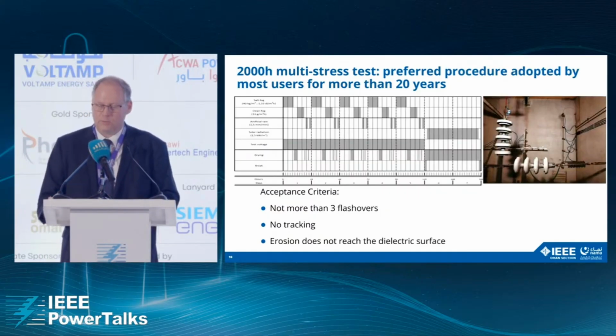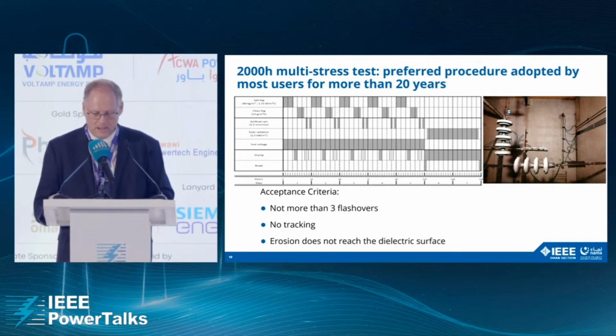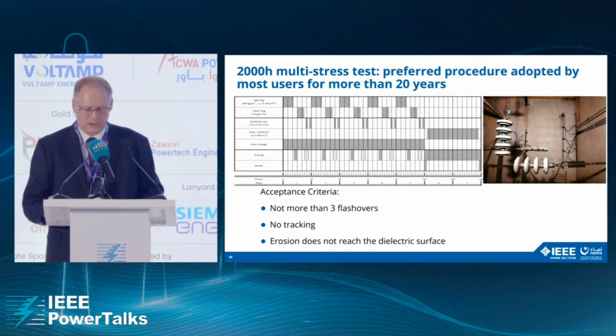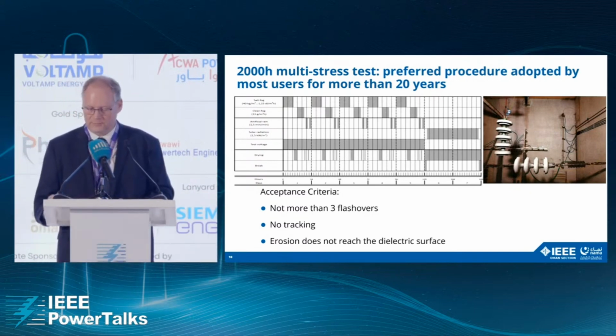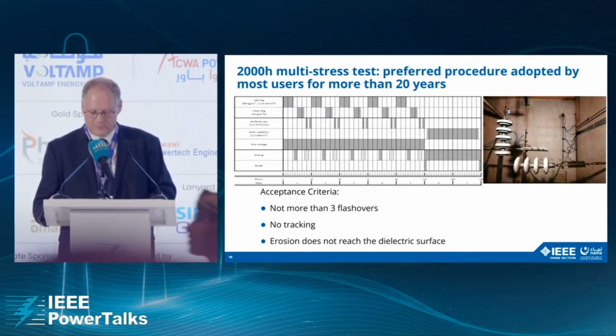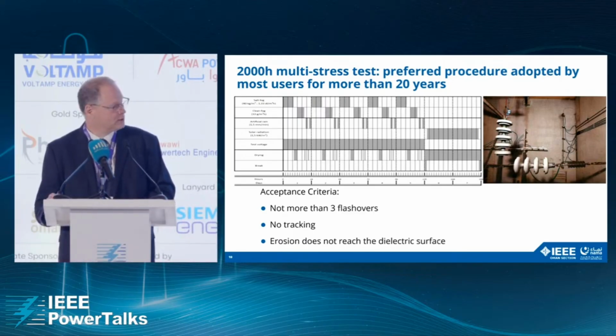But the 2,000-hour multi-stress test is today and by far the most frequently used and will most likely be included in the upcoming IEC standard. It is not a reduction of the 5,000-hour test, but follows a different protocol as shown here. The test combines periods of exposure to salt fog, clean fog, artificial rain, solar radiation, periods of drying, and periods of energization. The acceptance criteria of the test are the following: not more than 3 flashovers, no tracking, and the erosion shall not reach the dielectric surface of the insulator.